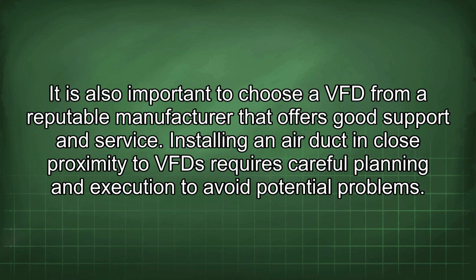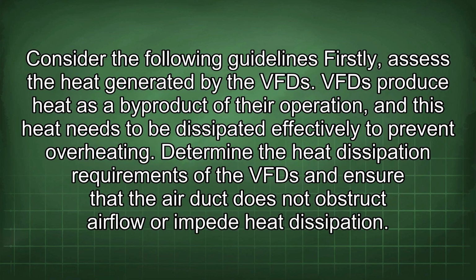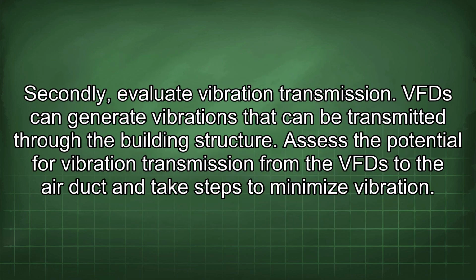Installing an air duct in close proximity to VFDs requires careful planning and execution to avoid potential problems. Consider the following guidelines. Firstly, assess the heat generated by the VFD. VFDs produce heat as a byproduct of their operation, and this heat needs to be dissipated effectively to prevent overheating. Determine the heat dissipation requirements of the VFD and ensure that the air duct does not obstruct airflow or impede heat dissipation.